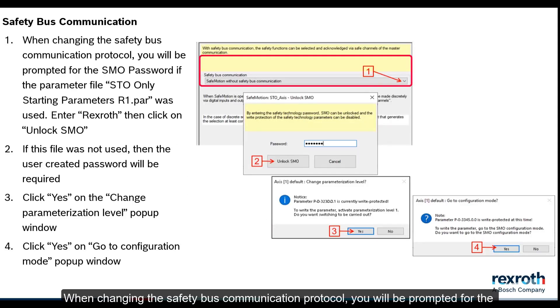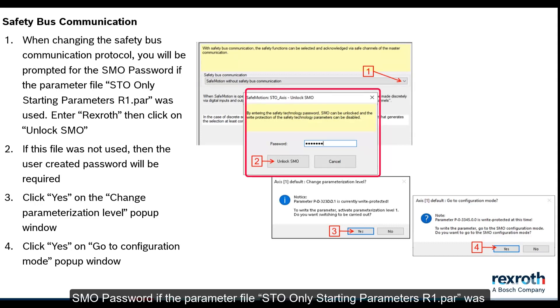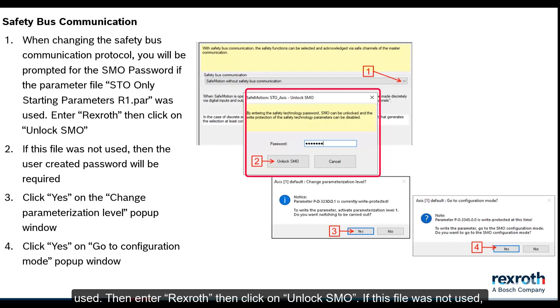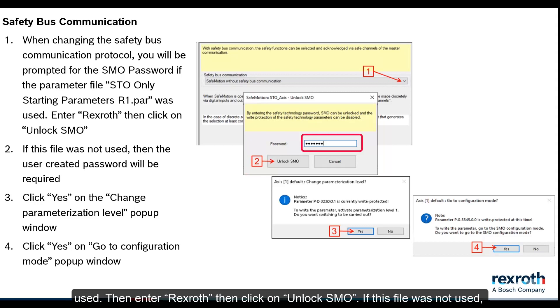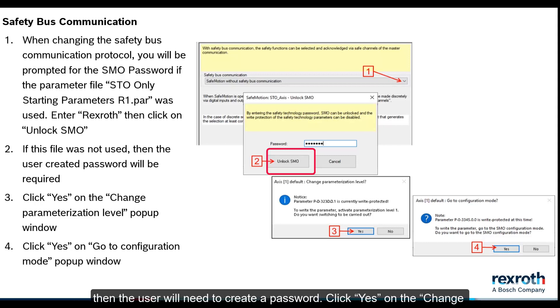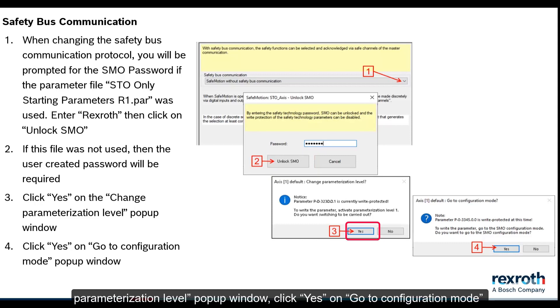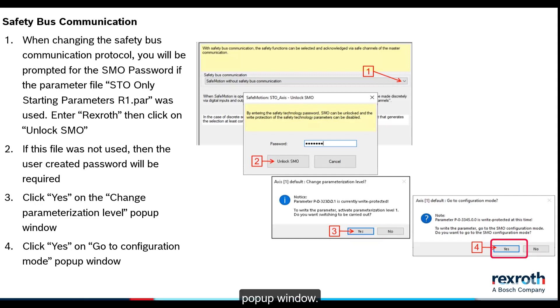When changing the safety bus communication protocol, you will be prompted for the SMO password. If the parameter file STO only starting parameters R1.par was used, then enter RexRoth, then click unlock SMO. If this file was not used, then the user will need to create a password. Click yes on the change parameterization level pop-up window. Click yes on the go to configuration mode pop-up window.